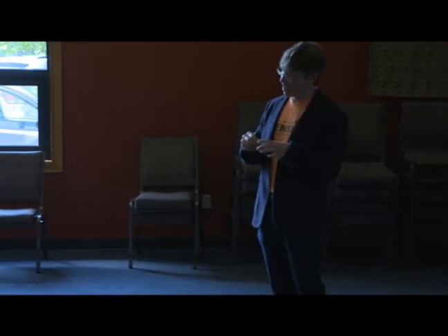The fact that the electricity is at twice the voltage means that it can arc further. It can actually, and this is probably something we should talk about, is we've already had a couple of instances where our current power lines have fallen down and electricity has arced into the pipeline. We already have 2 cases in the past 5 or 10 years where this has happened, and the electricity carved a crater in the pipeline casing that was bad enough that they had to shut down the pipeline and replace that section of pipe. Now, if it was twice the voltage, how much faster would it drill through the casing?